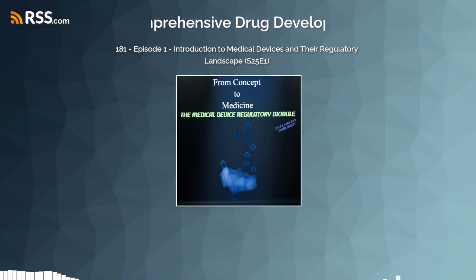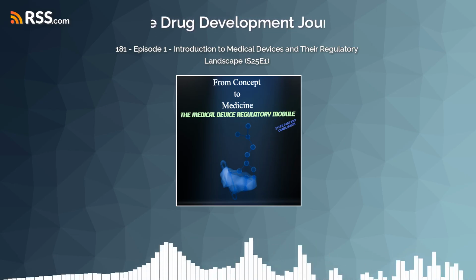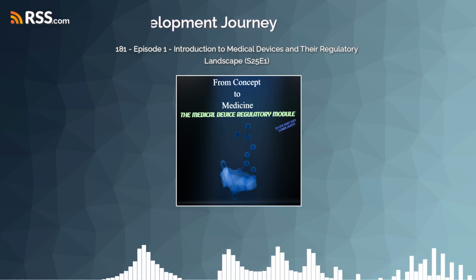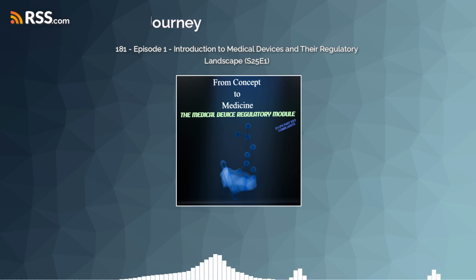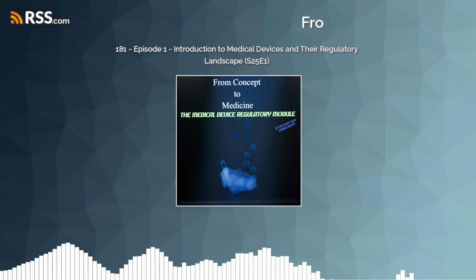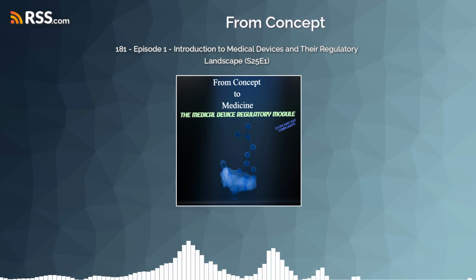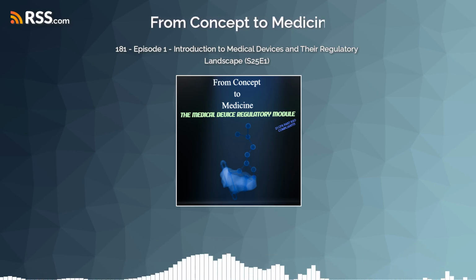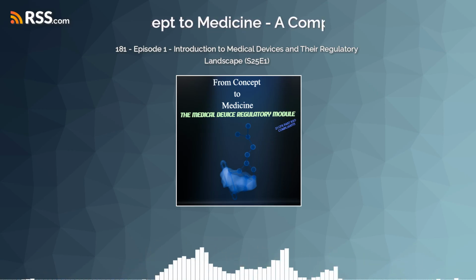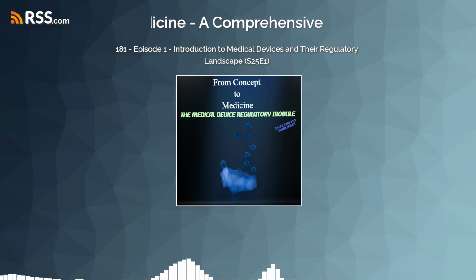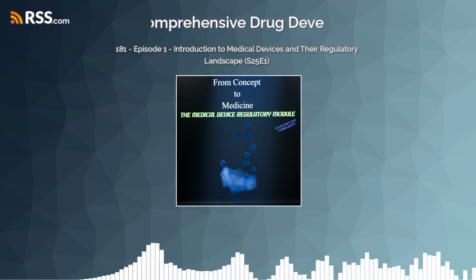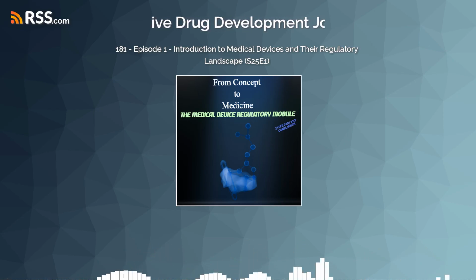SOPs for everything. Pretty much. It also includes stringent control over all the inspection, measuring, and test equipment used. And crucially, process validation. Process validation. What's that? That means establishing documented proof that a specific manufacturing process will consistently produce a product meeting its predetermined quality specifications. You have to prove your process works reliably every single time.